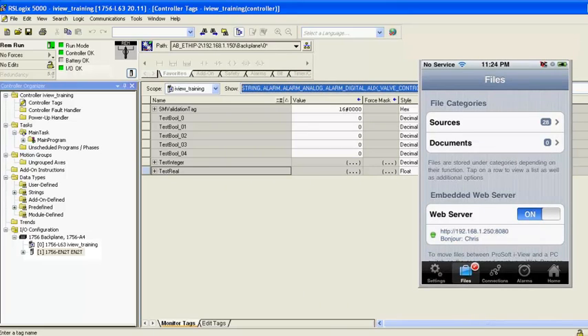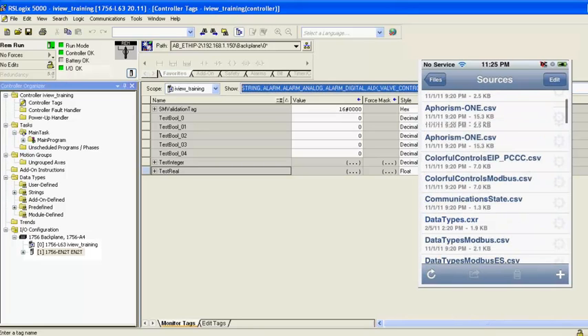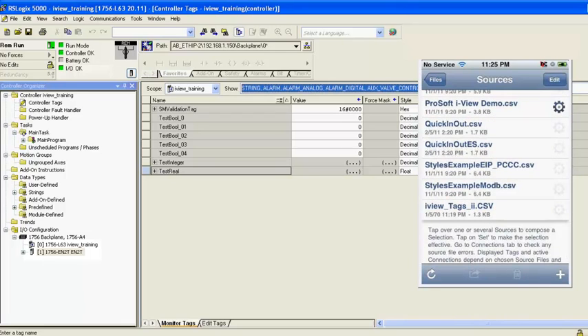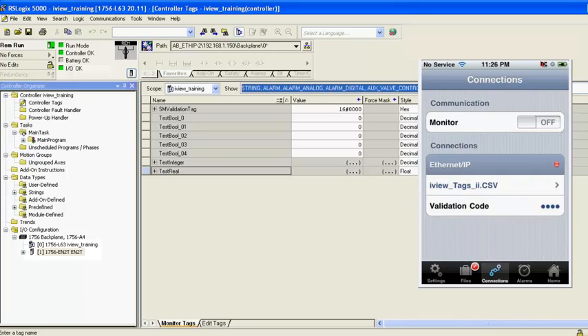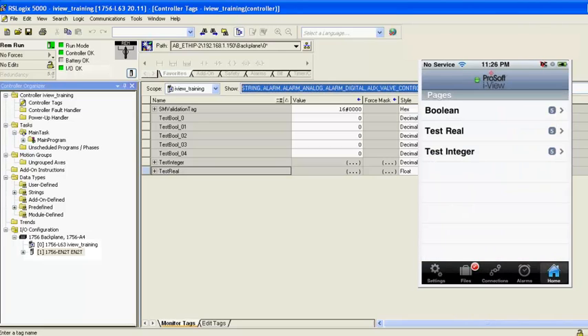Now that I have my project running in RSLogix, I'll go back to my iPhone and launch ProSoft iView and tap on the Files button. I'll click on the Sources tab under File Categories. When the Sources page loads, I'll select the iView Tags CSV file which I just uploaded, and the gear icon will show that it's active. Once I have the tags that I want selected, I'll tap the Set button. Then I'll tap on the Connections button. Once the connection page loads, I'll tap the Monitor toggle switch to place it in the On position. You'll notice that the Monitor indicator LED is green now, which shows that I'm connected.